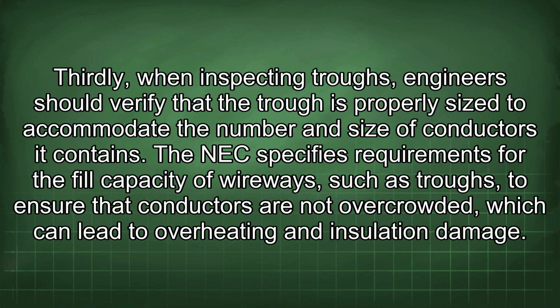Thirdly, when inspecting troughs, engineers should verify that the trough is properly sized to accommodate the number and size of conductors it contains. The NEC specifies requirements for the fill capacity of wireways, such as troughs, to ensure that conductors are not overcrowded, which can lead to overheating and insulation damage.